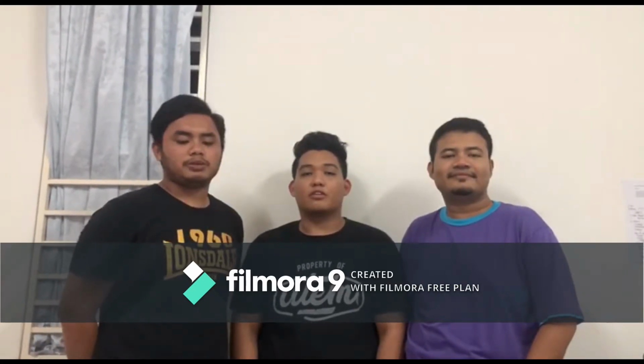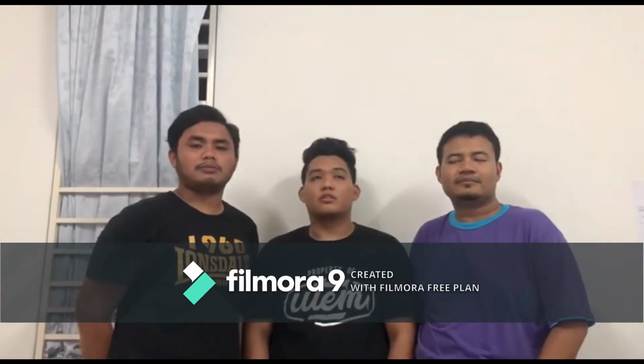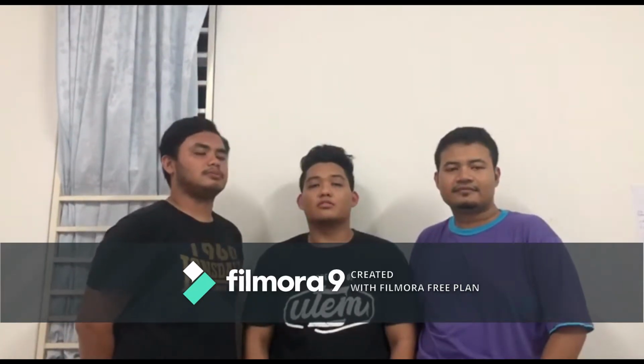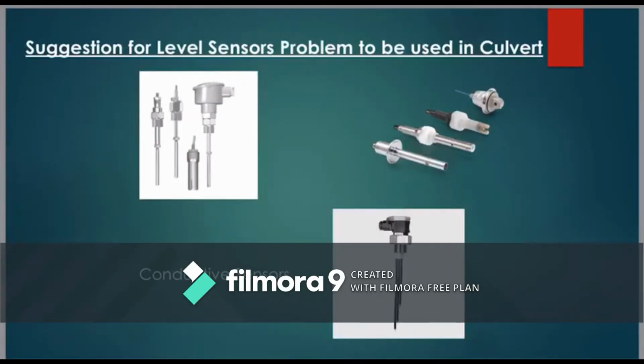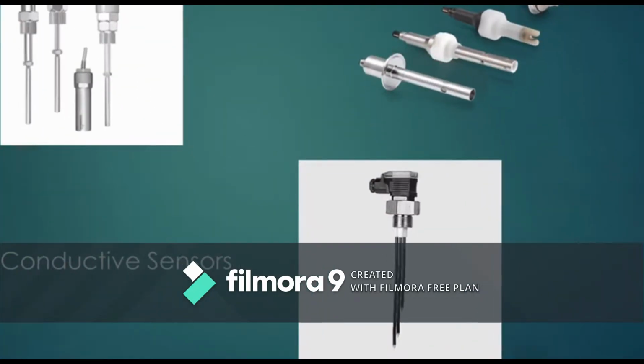So, our team will suggest a replacement sensor, which is conductive sensor, that would overcome the water leveling problem in culvert. Suggestion for level sensors problem to be used in culvert. So, our team has come up to choose for conductive sensors to be used in culvert to solve the level sensors problem. So this is the example of multi-level conductive sensors.